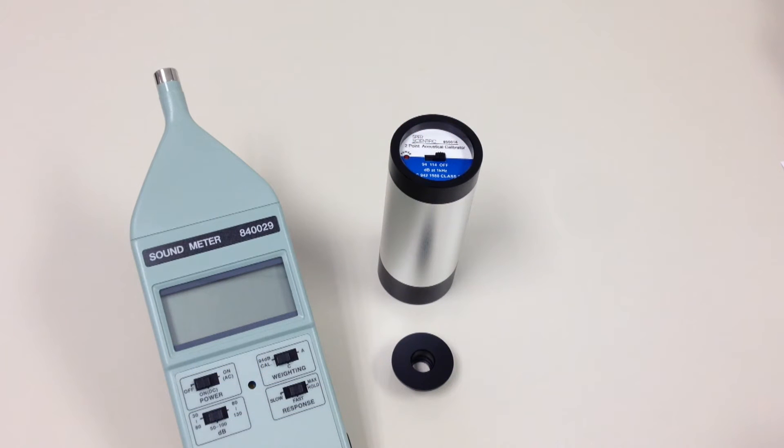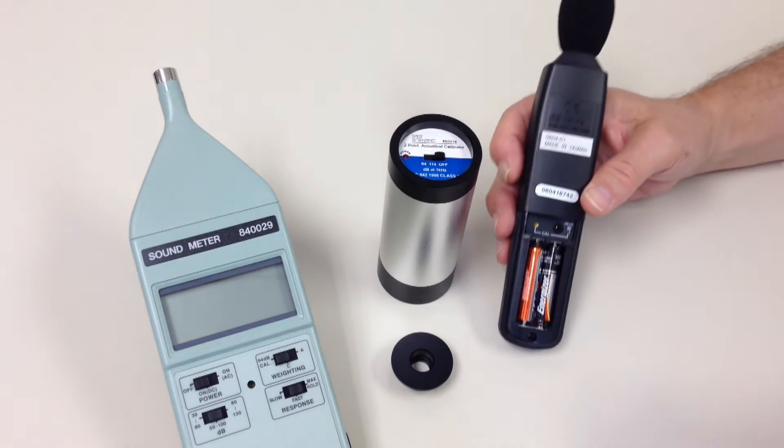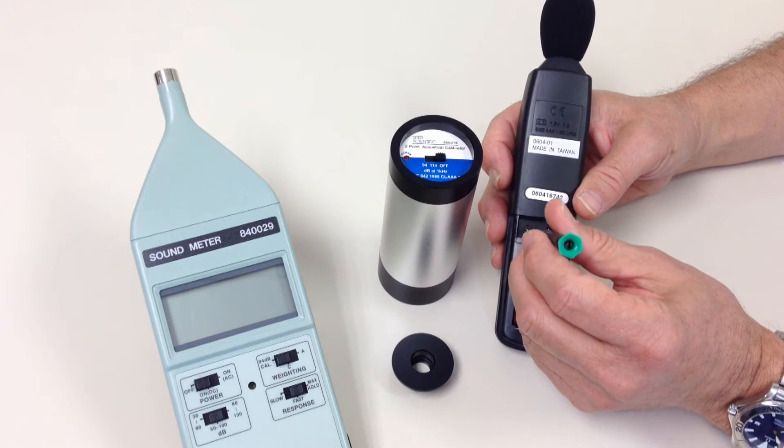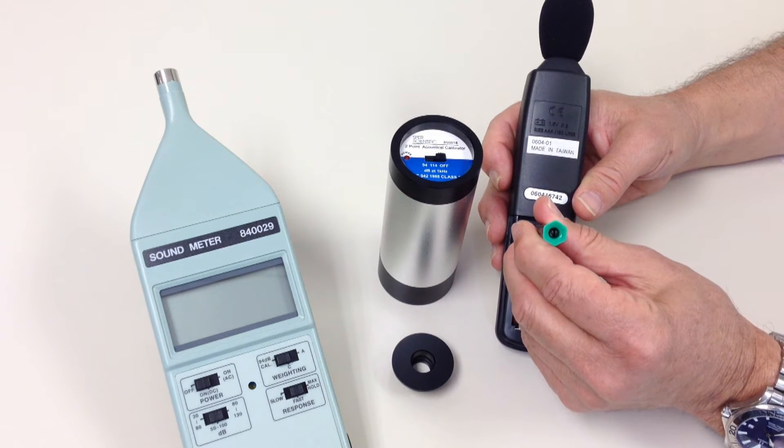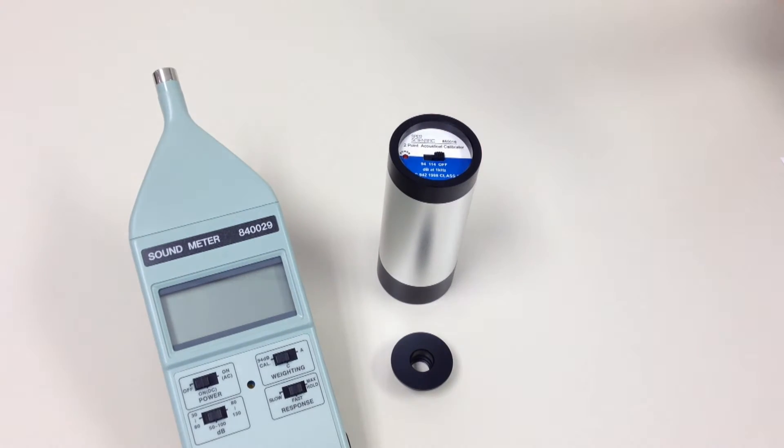All sound meters drift with time and require periodic recalibration. Some models have an internal oscillator that enables you to adjust the signal and correct the reading. But this doesn't take into account the microphone.